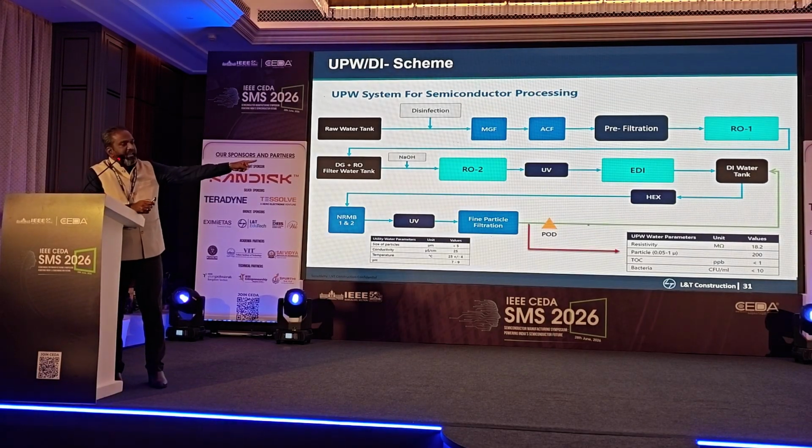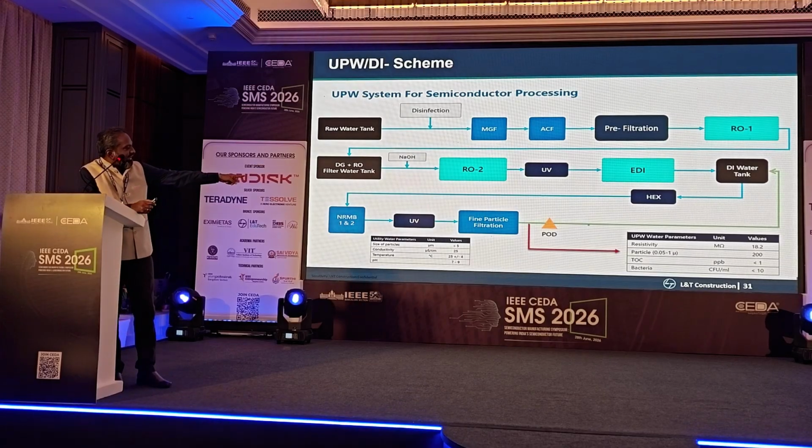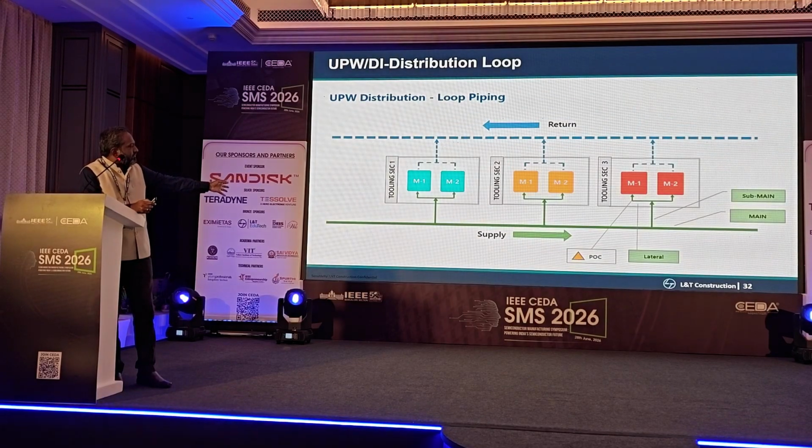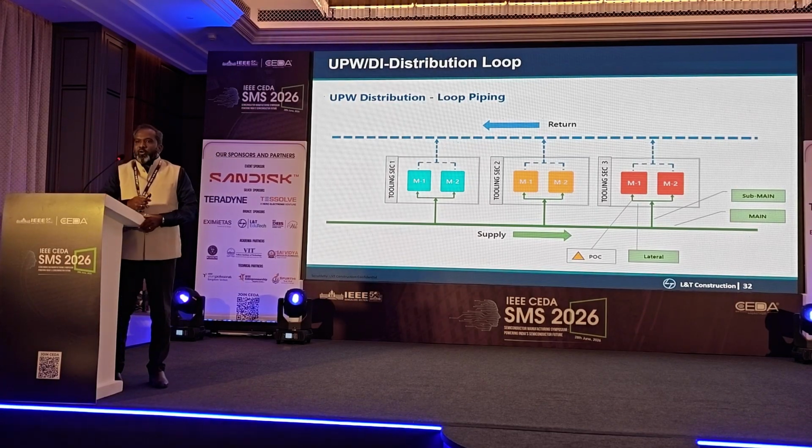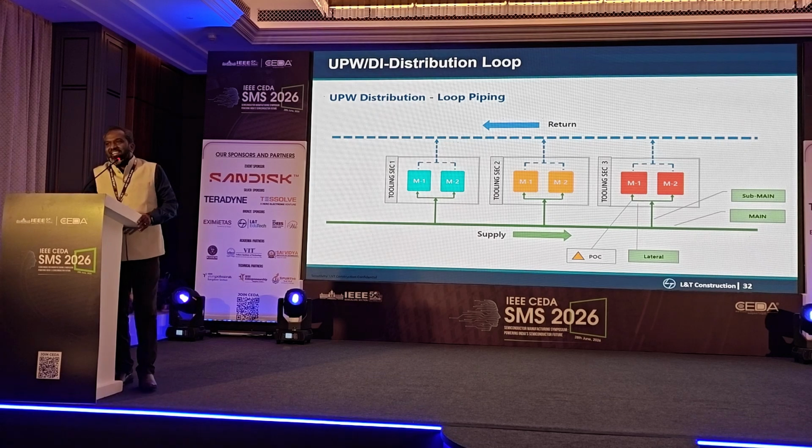you see the DI water tank. You see a green loop that is going there. So that's POU, the tools, basically. From that it goes to DI, and then this gets, we call it polishing. It's not filtration. For UPW we call it polishing.